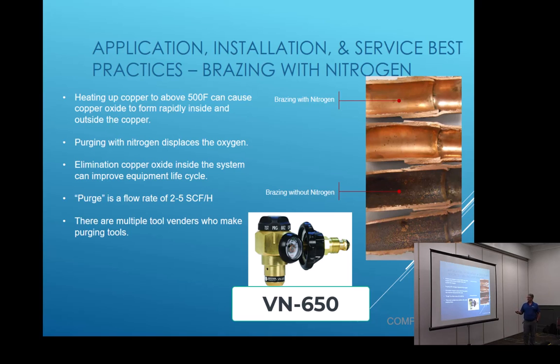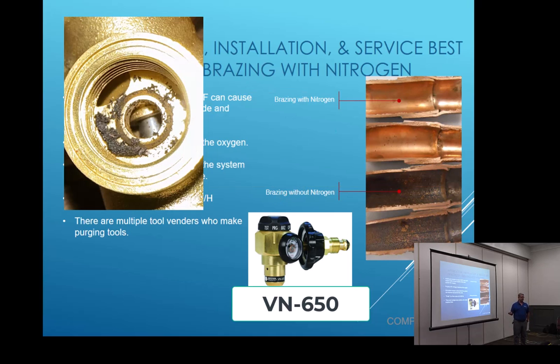Nitrogen regulator. This is a Uniweld that we sell at the branches. I don't care what brand nitrogen regulator you get, as long as the nitrogen regulator you get has a braze selection switch, a setting on it. Because if you go buy that $50 nitrogen regulator and you have to adjust the discharge and inlet on it every time, and you're over there trying to solder, oh, I got too much pressure. It blows out my flame. Oh, hold on. Oh, now I ain't got enough. I mean, you're going to leave that damn regulator in the truck and you ain't going to fool with it. So if you get one that has a braze selection on it, you just turn it to braze and it's automatically set. It lets the right amount out and you don't have to worry about it. Okay? And you don't have any problems. Okay? So we really need to start brazing with the proper tools.